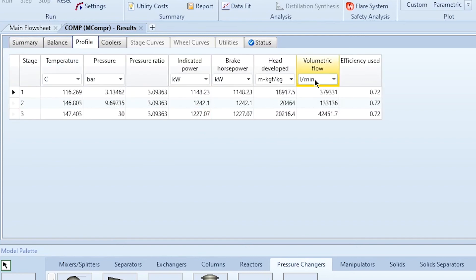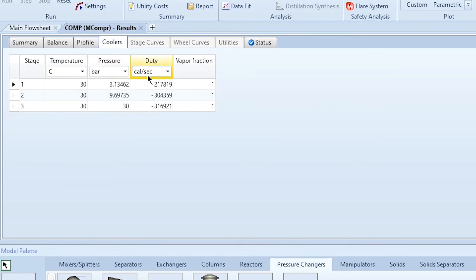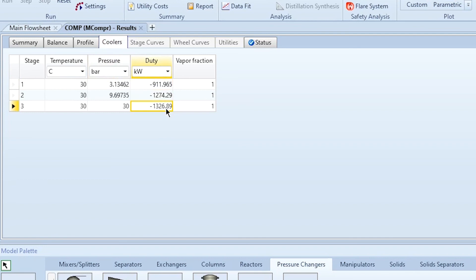The default isentropic efficiency used is 72%. If you want to specify a different efficiency value, you can enter it directly. The Profile also shows head developed, volumetric flow, and for each cooler the heat duties are calculated per compression stage, providing a very detailed analysis of the entire process.